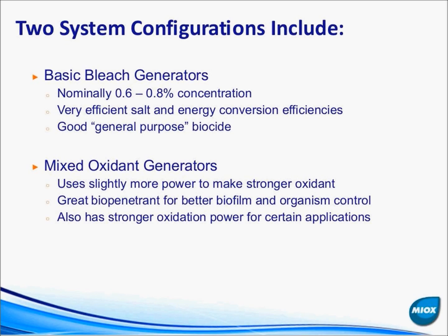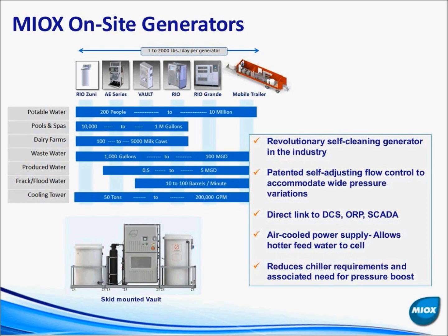Where we get into unique chemistry is our mixed oxidant series of generators. We have a separate webinar that covers these in detail, but in short: we use a different cell configuration to generate a stronger oxidant. That oxidant is a combination of sodium hypochlorite and hydrogen peroxide, and the trace hydrogen peroxide gives it some really unique chemistry characteristics.